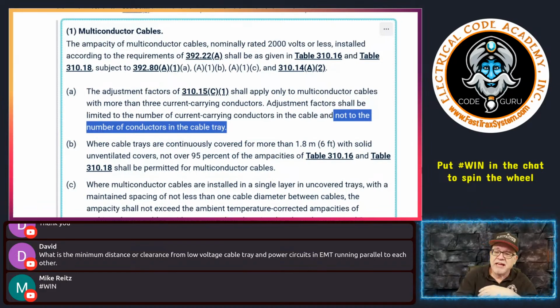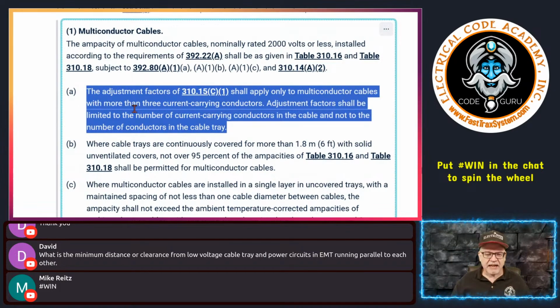That's huge because normally if we were to bundle cables, and you look at 310.15(C)(1), then if we bundle cables without maintaining spacing for over 24 inches, then we're going to have to apply an adjustment to that. Now, at the end of the day, I will remind you something: even though it says don't worry about it if your cables don't have more than 3 current carrying conductors, you don't have to apply the adjustments, and it applies to the cable and not the mass of cables inside of it, you still got to meet all these rules here.